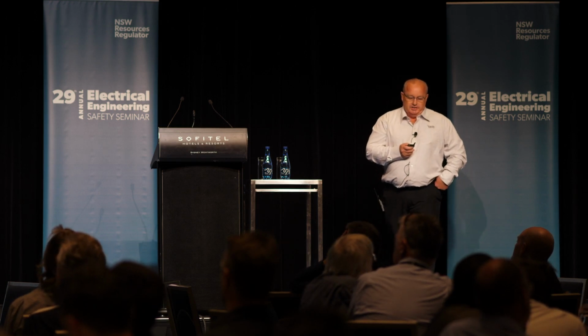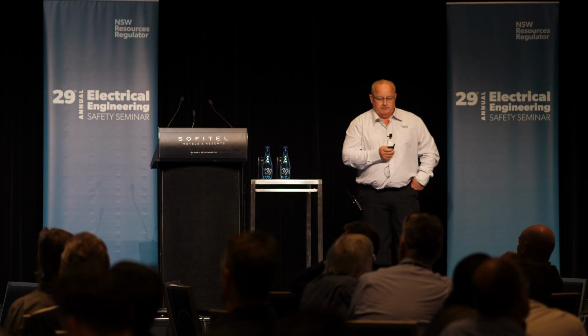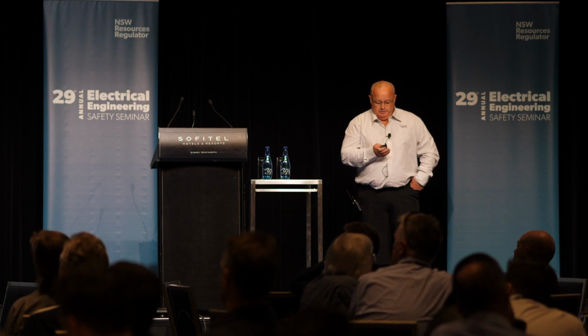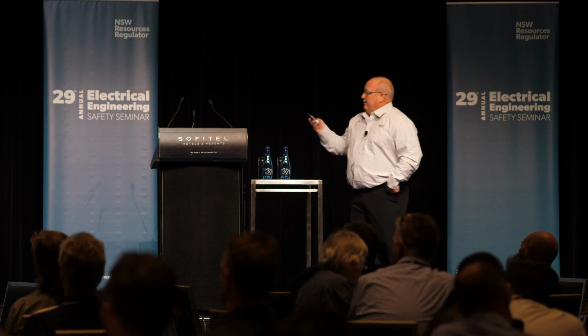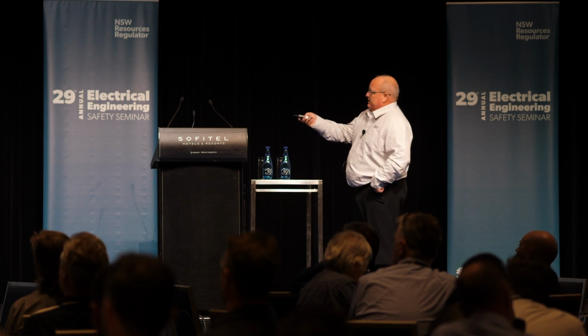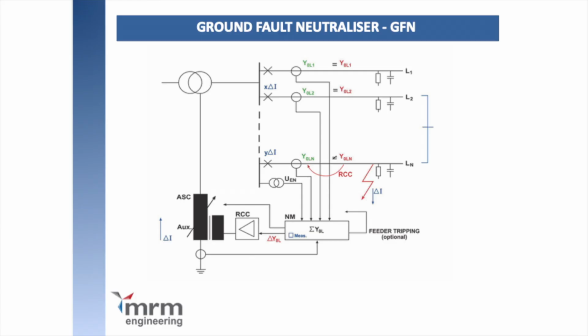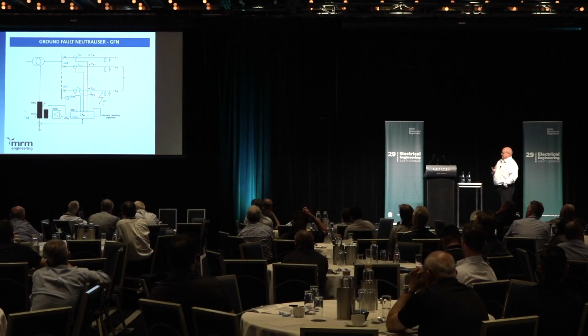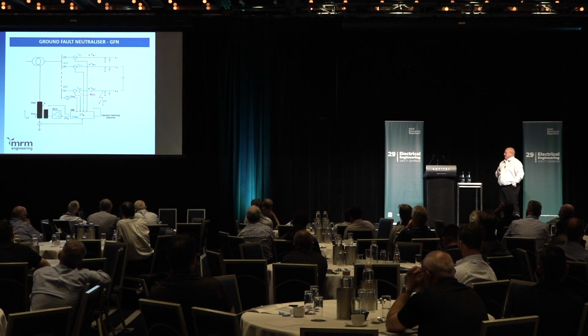So the ground fault neutralizer, this is just a three-phase diagram of it. So you can see, where is the pointer? So you can see up in the top there, you've got the 3 monitoring CTs. The red is your residual current compensation. In the green there, you've got the capacitive currents that would flow, and the residual current compensation is done by the unit, by the ground fault neutralizer, to align the network capacitance so you get a zero current flowing via the capacitance in the network.